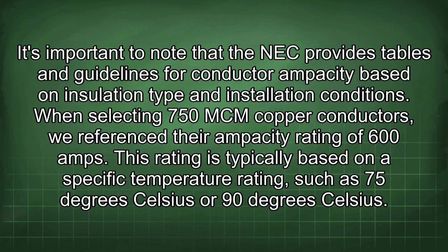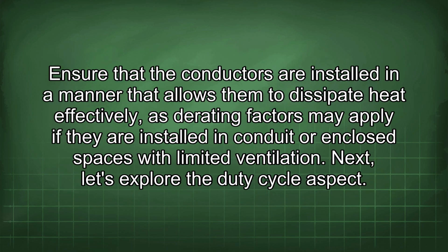It's important to note that the NEC provides tables and guidelines for conductor ampacity based on insulation type and installation conditions. When selecting 750 MCM copper conductors, we reference their ampacity rating of 600 amps. This rating is typically based on a specific temperature rating, such as 75 degrees Celsius or 90 degrees Celsius. Ensure that the conductors are installed in a manner that allows them to dissipate heat effectively, as derating factors may apply if they are installed in conduit or enclosed spaces with limited ventilation.